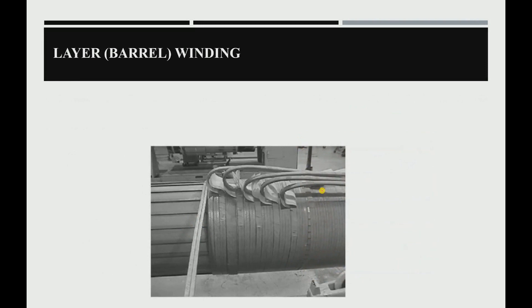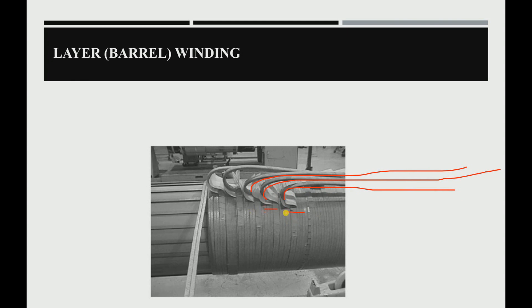The third formation is called the layer or barrel winding. This formation is used in the tap changer transformer — that is, a transformer with a tap changing function. You can see this part going outside the transformer, which represents the taps. You can count one, two, three, four, five — five taps — and the tap changer is used to change the number of turns of the transformer.